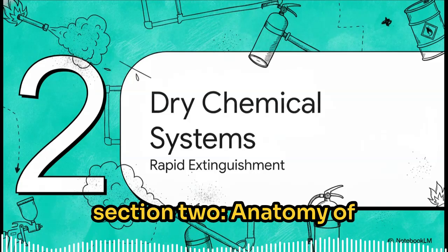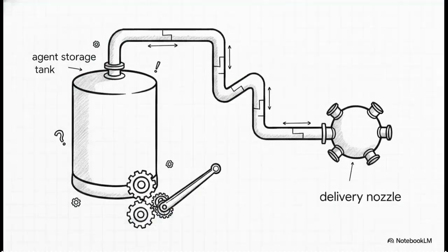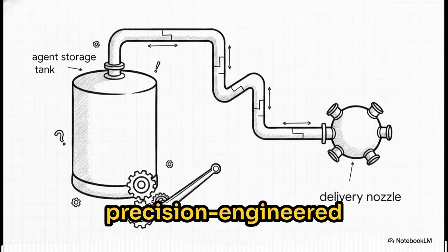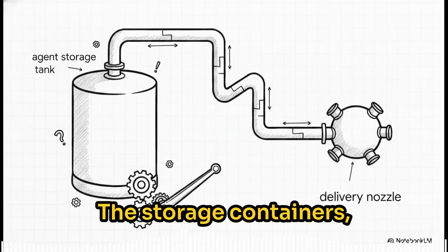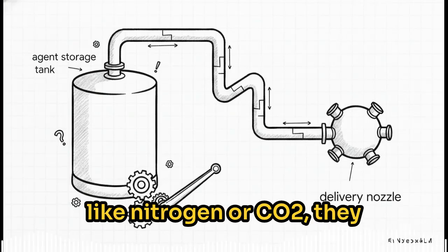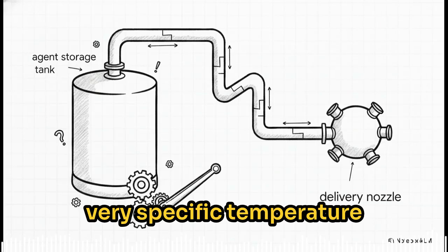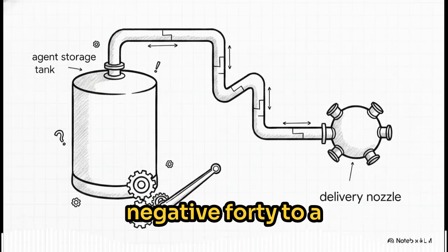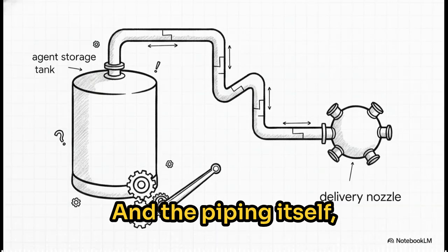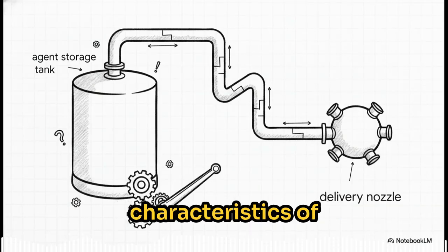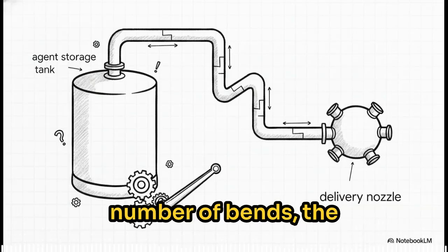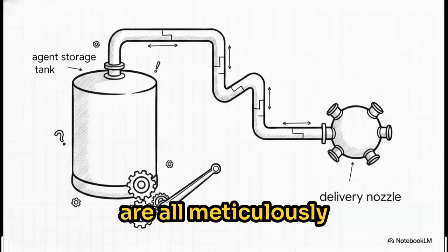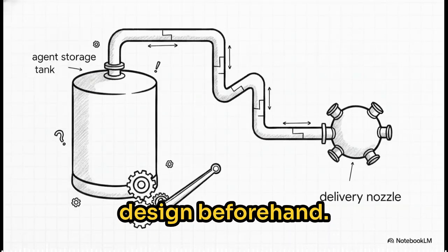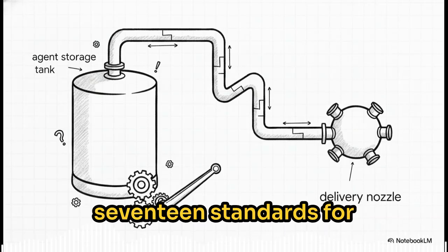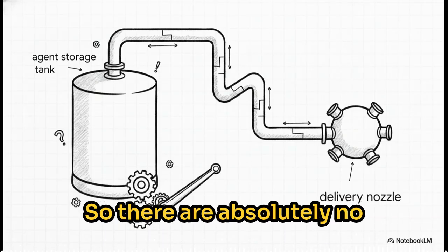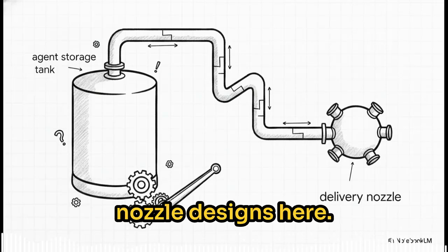Moving right along to section 2, anatomy of dry chemical systems. Now, what's really fascinating here is how incredibly precision engineered these setups are. The storage containers, which hold the agent and a pressurized expellant gas like nitrogen or CO2, have to be maintained in very specific temperature ranges, typically from -40 to 120 degrees Fahrenheit. And the piping itself is mathematically engineered to account for the unique flow characteristics of the chemical agent. That means the exact number of bends, the fittings, and the pressure drop or friction loss are all meticulously calculated into the design beforehand. Even the nozzles must be specifically listed by NFPA 17 standards for their exact intended use. So there are absolutely no standard one-size-fits-all nozzle designs here.